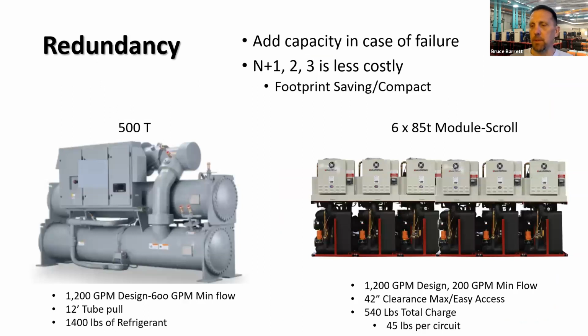So let's talk about that redundancy component. We've done a number of changeouts or engineered solutions when we've compared a singular 500-ton chiller to an array of modular water-cooled chillers. And doing the calculations of refrigerant charge, for example, a 500-ton chiller would have approximately 1,400 pounds of refrigerant. The same capacity of a modular array would have about 540 pounds of charge, with the smallest circuit being 45 pounds of refrigerant. So I haven't run into a mechanical room yet that has had modular scroll chillers on braze plate heat exchangers with that very small micro charge that has required the ventilation component to comply with ASHRAE 15. We'll talk a little bit more about that later.